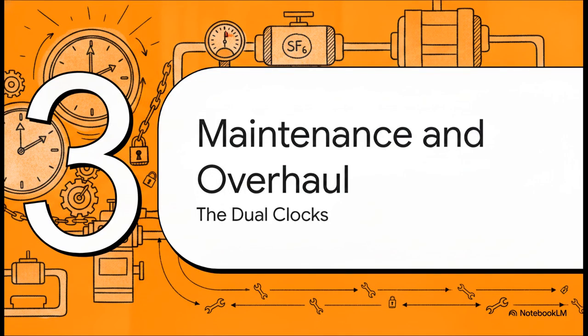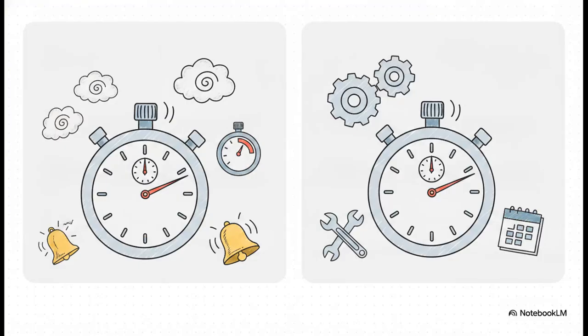Section 3. Maintenance and overhaul. The dual clocks. And this brilliantly illustrates why maintenance requires such strict discipline. You're basically managing two separate timelines, two concurrent clocks ticking away on every single HPA breaker. First, you've got your gas checks. These are operations-based. You verify pressure at commissioning, then after 7,500 operations, again at 10,000 operations, or obviously immediately if that density relay alarm sounds.